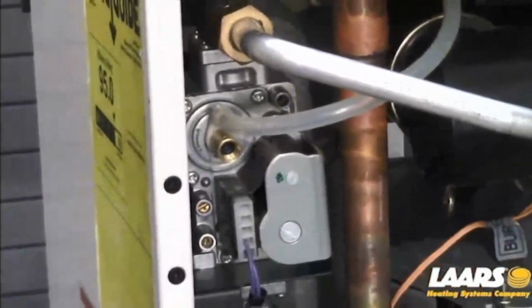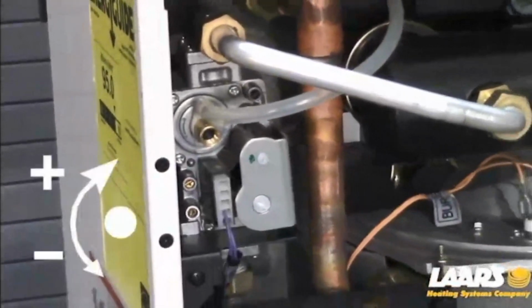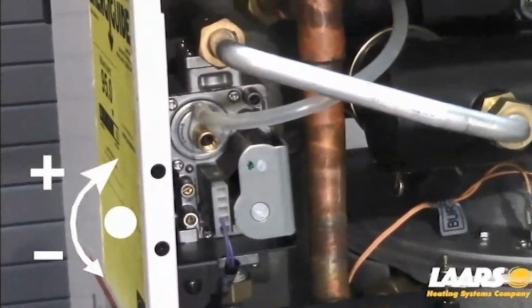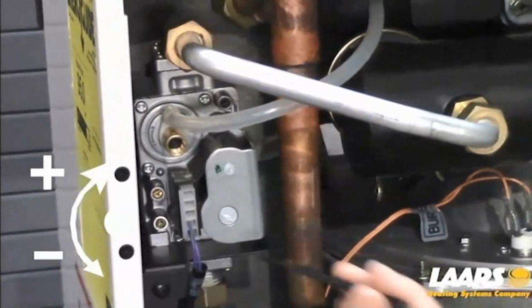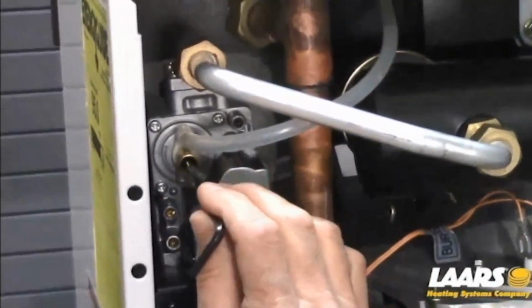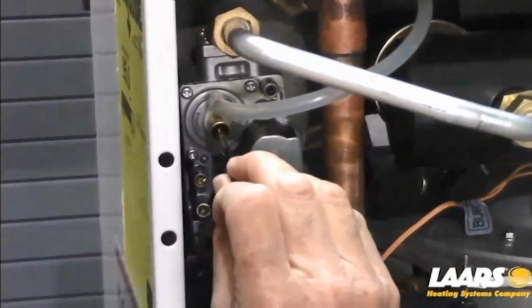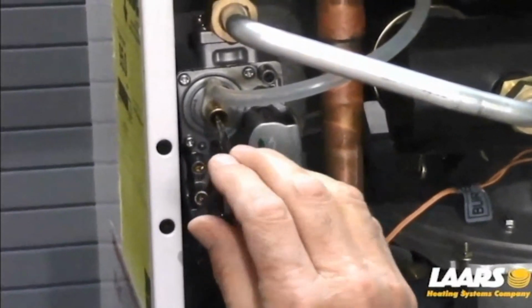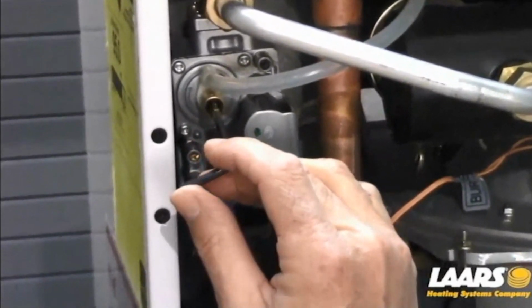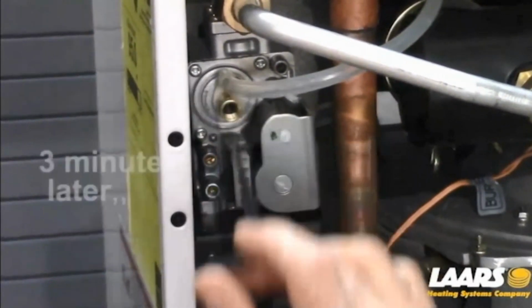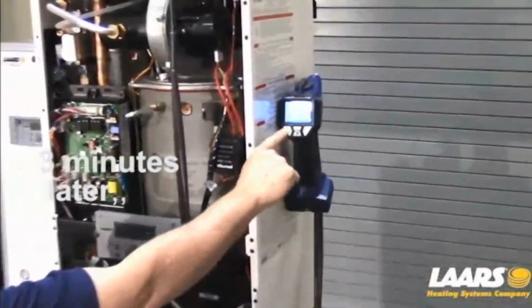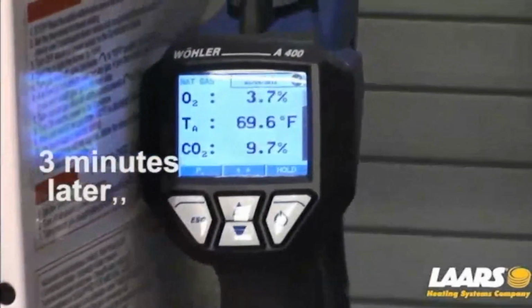And right on the valve, it's going to show you clockwise will increase, counterclockwise will decrease. Well, we know we had to make a clockwise or increase adjustment. So what I'm going to do is just take a very small adjustment. So we made our low fire adjustment. What we want to do is be very patient with your analyzer. Make sure we're within range for low fire.